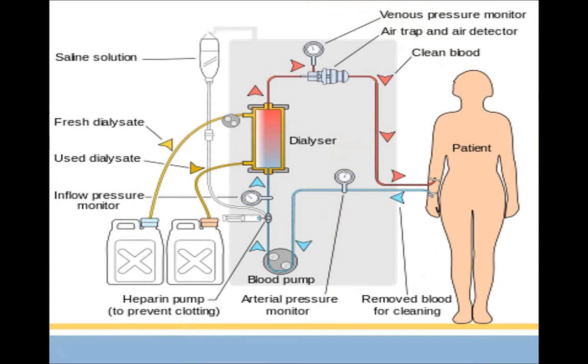This diagram represents a general hemodialysis setup, and the grayed area represents the dialysis machine. Depending upon the machine, if a person wants to explore home options, supplies would be needed, which would include filters, solution, disinfectant, syringes, needles, medicines, blood tubes, water test kits, water treatment tanks. Some machines require electrical and plumbing modifications in the area where the dialysis will be done, and also a backup plan for emergencies like power outages.